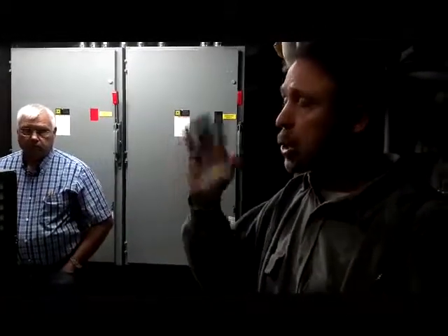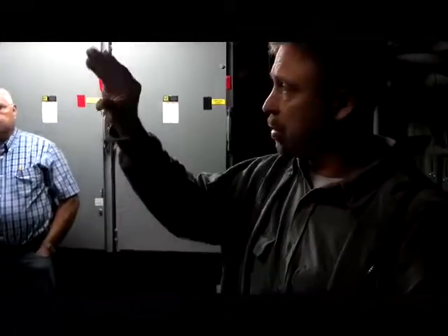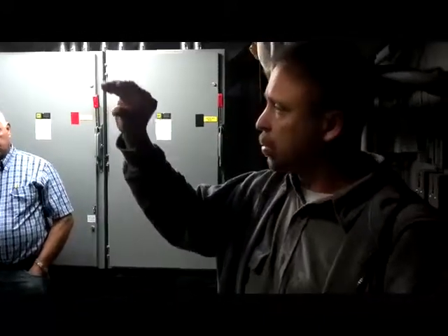Steve or Roger or John might come in there and have to boost the pressure up to get that radiator hot. That's the last thing you want to do. The first thing you want to do is fix that trap. Remember, going from 4 pounds to 8 pounds steam. If you have 4 pounds of steam running perfectly all the time, and you have to bump it up to 8 pounds, you're putting 8 pounds of pressure instead of 4 pounds on all those traps, so the longevity of your traps will diminish over time. You'll lose the life of your traps quicker. They're mechanical devices that go up and down, so if you're pushing on them with 8 pounds, it's shortening the life of your traps.